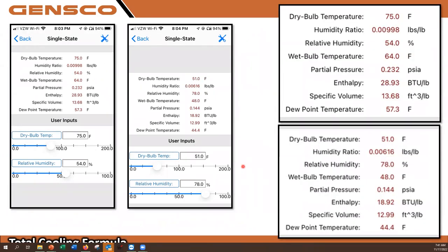Notice here also the specific volume of air that's shown. In the return air, it's 13.68 cubic feet per pound. And in the supply air, remember I said it got denser, it's 12.99 cubic feet per pound. If we were in heating mode, the supply air would be higher than the return air. This is why, if you're on a ducted unit and you want to do air balancing and measure CFM, for this particular exercise you don't want the unit running in heating or cooling. You want it in fan mode so there is no state change of the air as it goes through the unit.